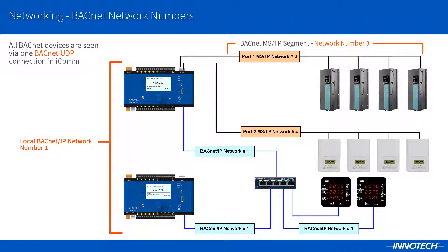As additional BACnet network segments are created — in this case by adding a new MSTP connection to the Omni controller — the network number must be checked and configured. In this example, I have assigned network number 4 to the new segment. All the BACnet devices will be discovered via the BACnet connection in ICOM.